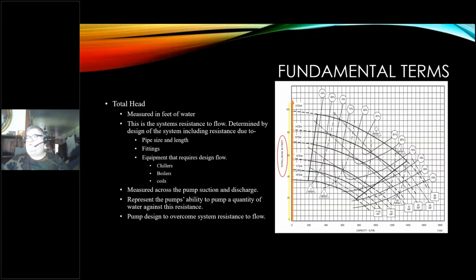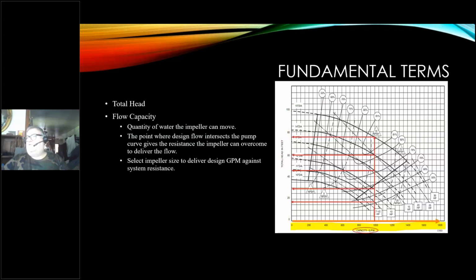Remember this. We'll bring this up multiple times as we start talking about flow. The flow is across the bottom, so this is the capacity that these curves will produce. If you draw straight up, let's say in this case from 1,000 GPM, to where it intersects each one of these curves, and you move to the left, you'll notice where it intersects the line for the pump head. Take our 15-inch diameter curve as an example. At 1,000 GPM, it will move 1,000 GPM somewhere in the 75 feet range.